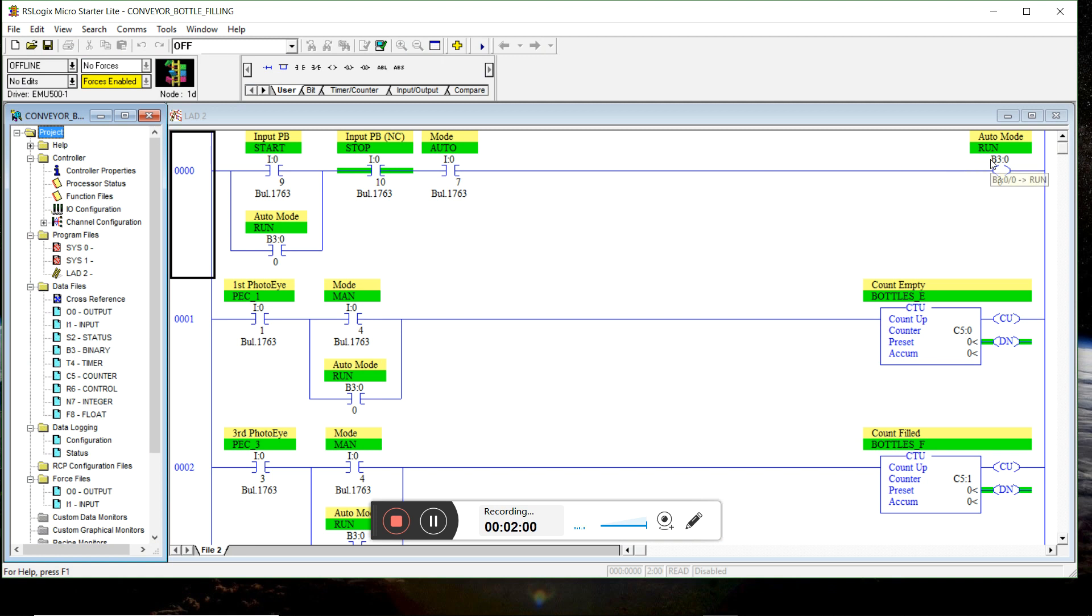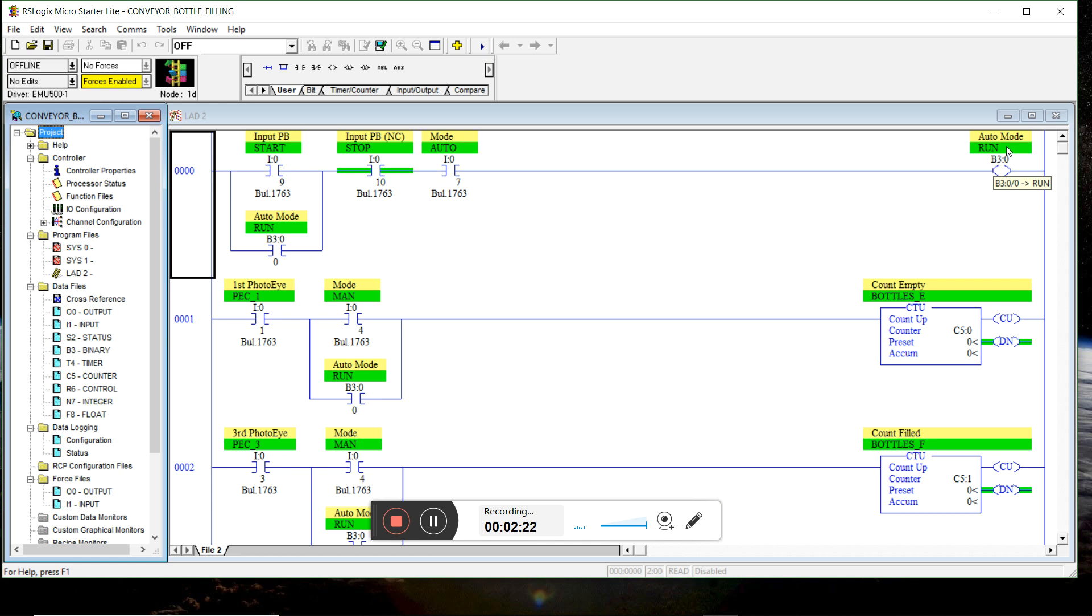Actual sequence of automatic operation doesn't actually begin just by putting it to auto. You have to hit the start push button for it to work. So because of that, I defined an internal bit called auto run mode. And we have to be in auto to be able to do that. And once we hit the start push button, it seals.